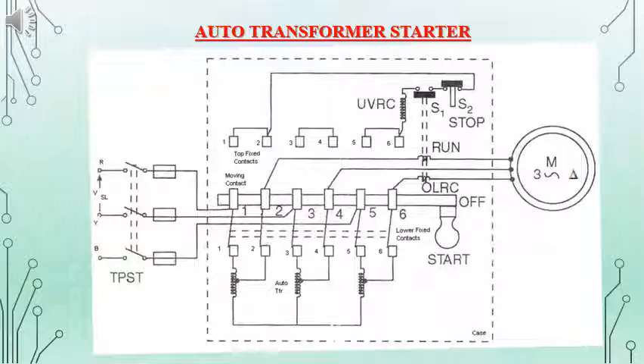At the start condition, the moving contact will be closing the lower fixed contacts, by which the supply to the stator terminals of the machine will be provided through the auto transformer. Once the machine picks up speed, the switch can be turned from start condition to run condition, where the entire voltage will be applied across the stator terminals. There are protective mechanisms for under voltage and overload. At under voltage condition, at run position, the relay coil will open up the switch, and for overload condition, the relay coil will be activated and will open the switch S1, or the machine can be switched off by using the stop switch S2.